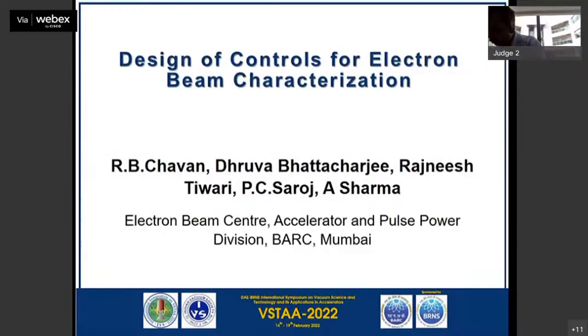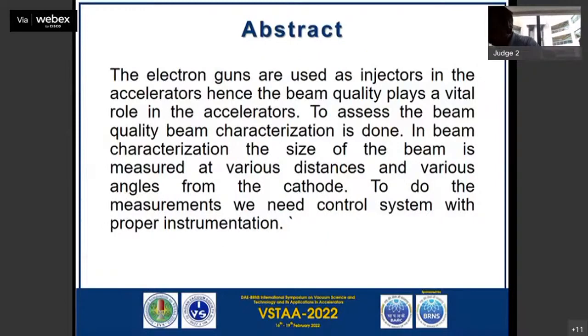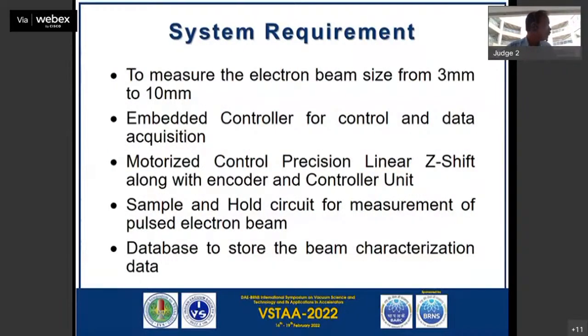Yes, sir. So my next paper is design of control for electron beam characterization. Next, please. The electron guns are used as an injector in the accelerator, hence the beam quality plays a vital role. To assess the beam quality, we are doing the characterization. In beam characterization, the size of the beam is measured at various distances and various angles from the cathode. To do that, we need a control system with proper instrumentation. Next, please. The system requirements are to measure a beam size of 3 mm to 10 mm, an embedded controller, a motorized precision Z-shift linear encoder with a control unit to move the linear stage in micron steps, sample and hold to measure the pulsed electron beam, because we are characterizing the pulsed electron beam, and a database to store the beam characterization data.